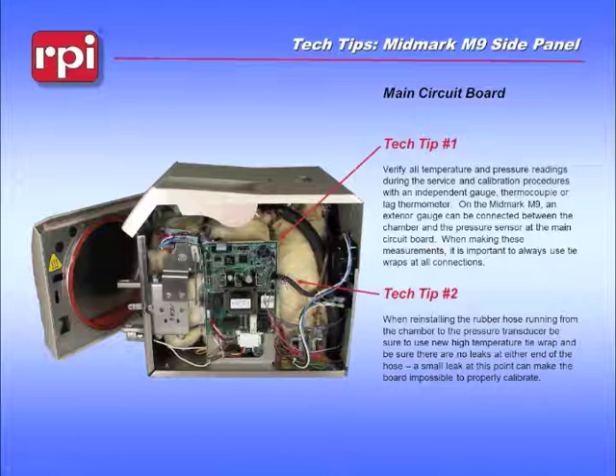This neoprene tubing is held in place by 2 tie wraps. These 2 tie wraps are critical. They must be in place. Even if you're just doing some diagnostic with the machine or testing, these tie wraps need to be here. A leak at this point in the system, even a very small leak, will throw the whole machine's readings off and can be very problematic.